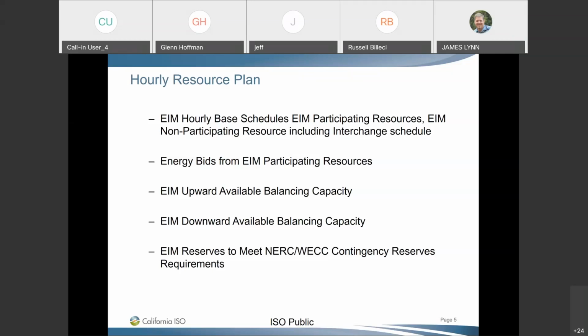Now, that regulation energy is limited by that available balance capacity for reg up or reg down. So let's say this unit has 10 megawatts of uninstructed imbalanced energy. So they scheduled 100, meter was 110, and it got no dispatches through the market. Well, for that 10 megawatts, I'm going to look to see, did you have any regulation up associated with that resource?